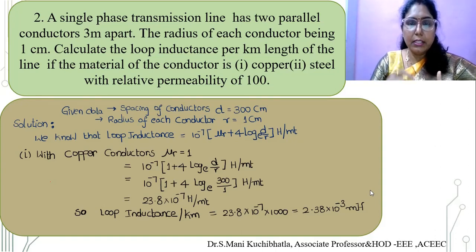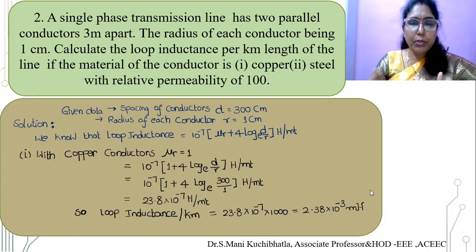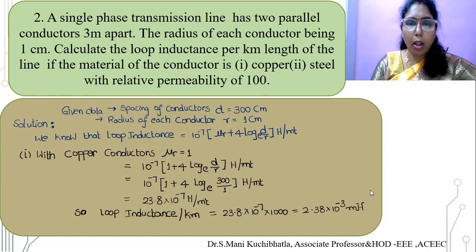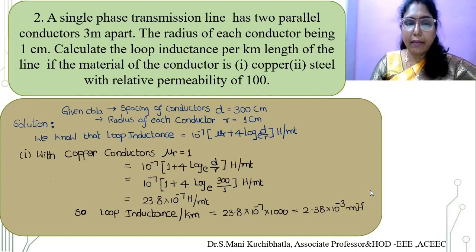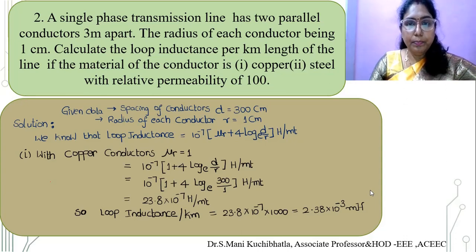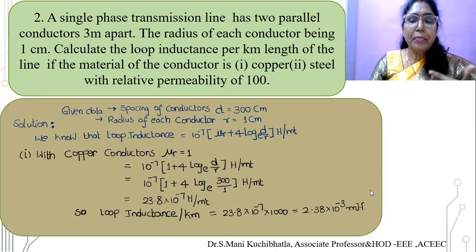First we go with the copper conductors where the relative permeability mu_r is 1. Substituting: 10 to the power minus 7 into (1 plus 4 log to the base e of 300/1) henries per meter, where d is 300 and r is 1 centimeter. After simplifying we get 23.8 into 10 to the power minus 7 henries per meter. Multiplying by 1000 for per kilometer length, we get 2.38 millihenries.